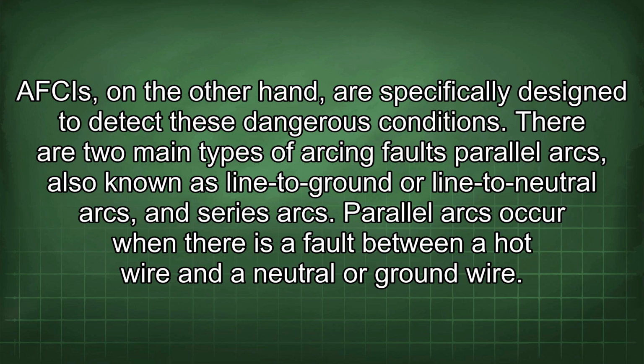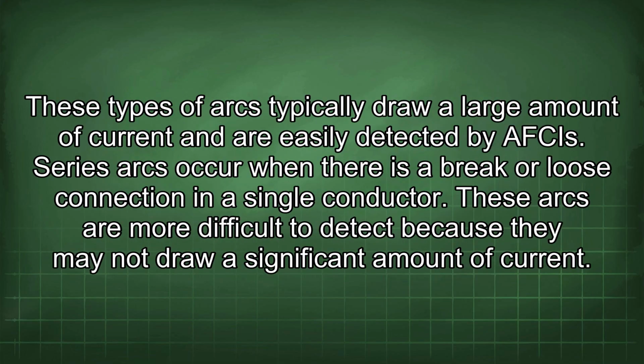There are two main types of arcing faults: parallel arcs, also known as line-to-ground or line-to-neutral arcs, and series arcs. Parallel arcs occur when there is a fault between a hot wire and a neutral or ground wire. These types of arcs typically draw a large amount of current and are easily detected by AFCIs. Series arcs occur when there is a break or loose connection in a single conductor. These arcs are more difficult to detect because they may not draw a significant amount of current.